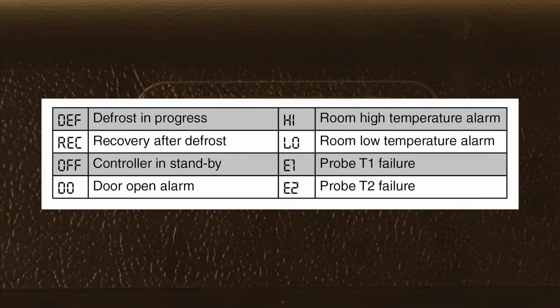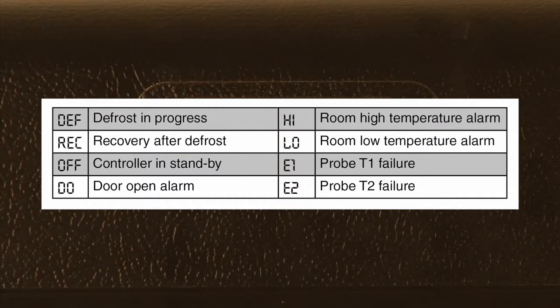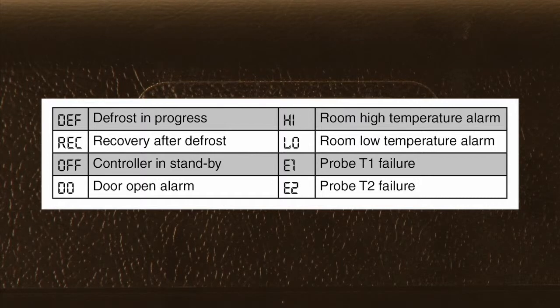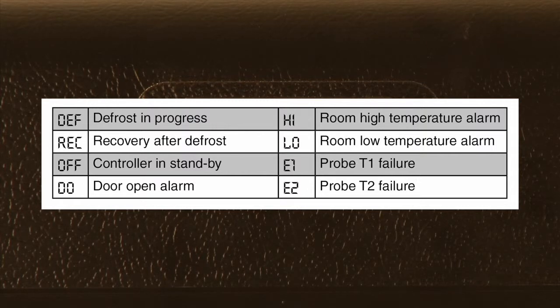If you see OFF, that means the unit has been put in standby — while it's powered, the refrigeration system will not be operating. Should someone leave a door open, DO will appear, which is the door alarm. If you have a high or low temperature alarm in the cabinet space, the readouts will indicate HI and LO.